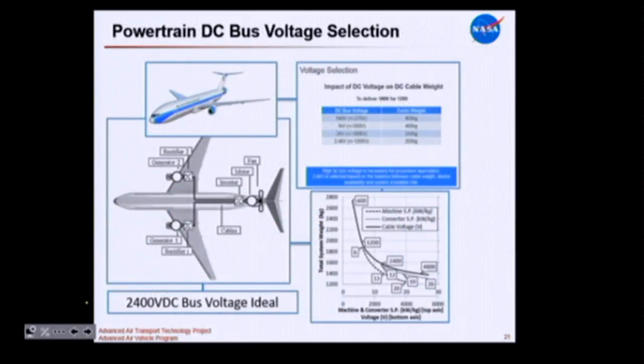As I mentioned, a higher bus voltage is ideal. You can see here 200 kilograms of cable weight at 2.4 kilovolts versus 240 kilograms at 2000 volts. As you lower the voltage of the DC bus, the cable weight increases, because lower voltage means more current, and more current means bigger cables.